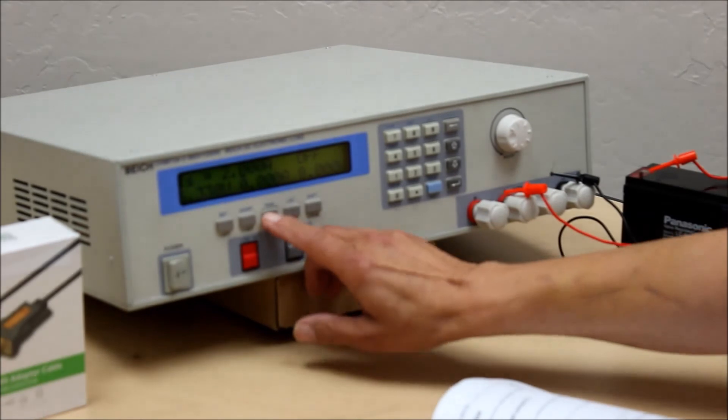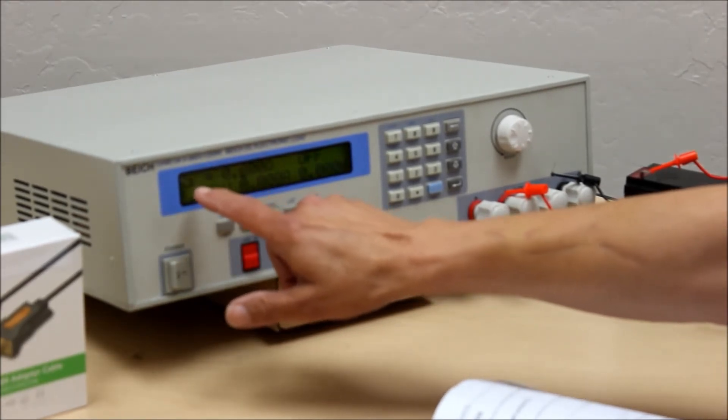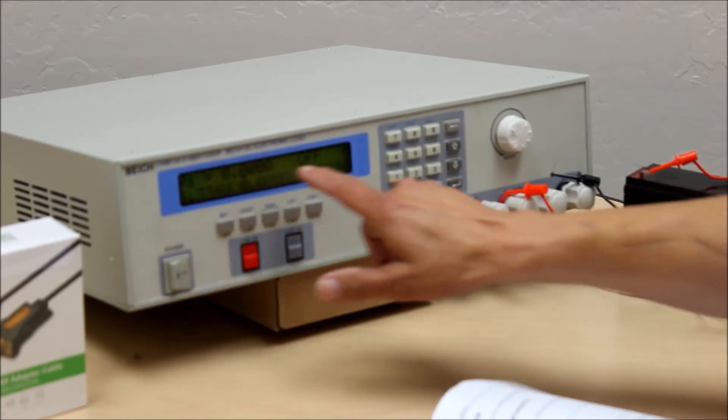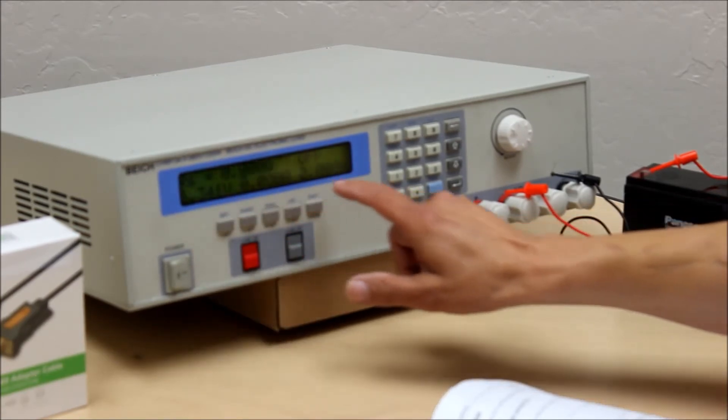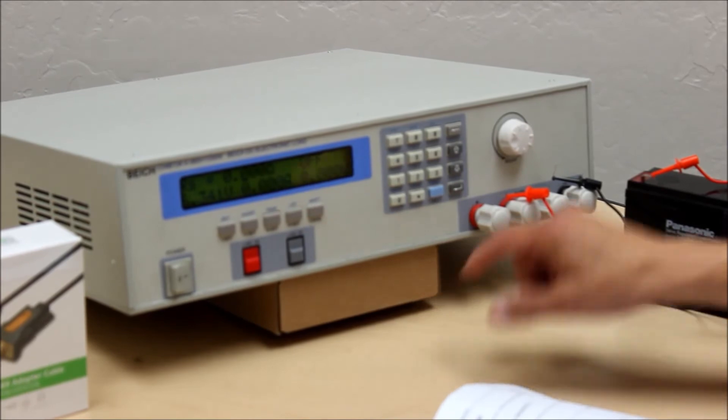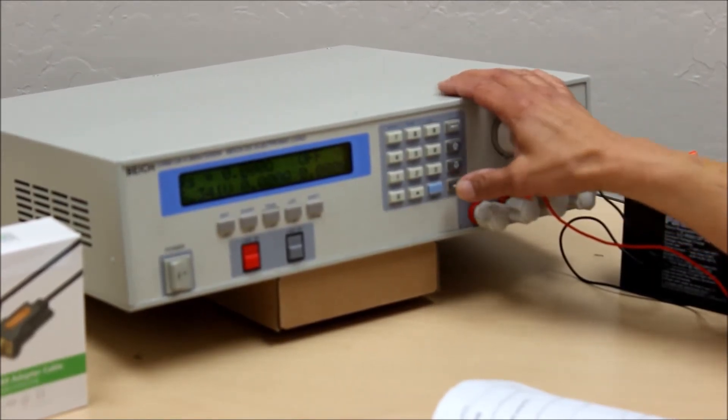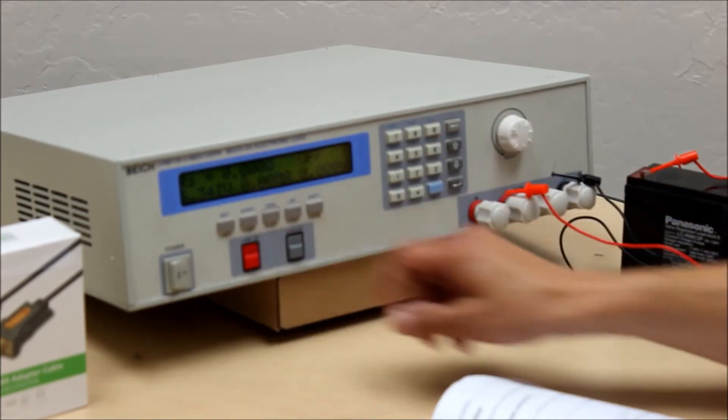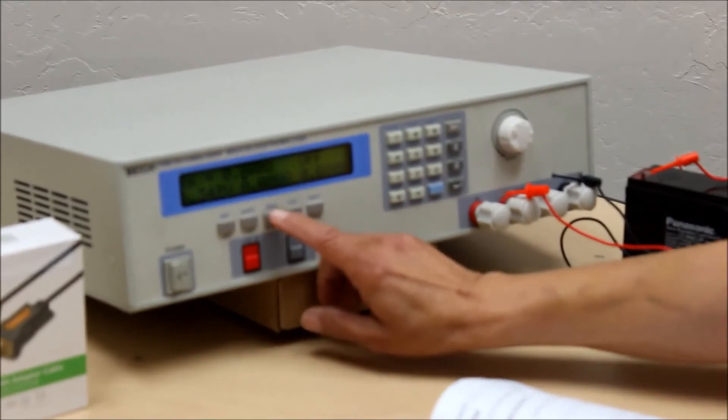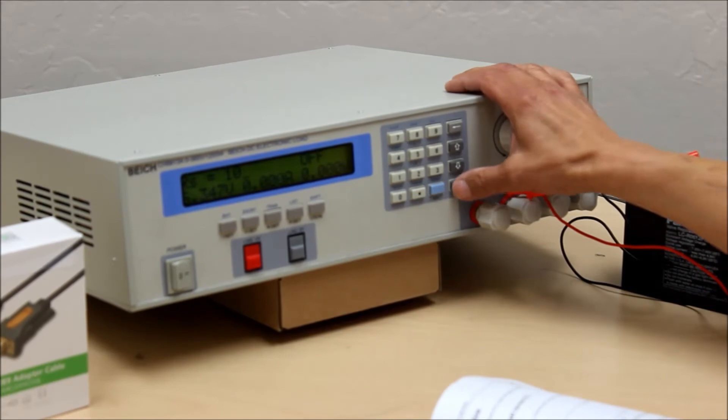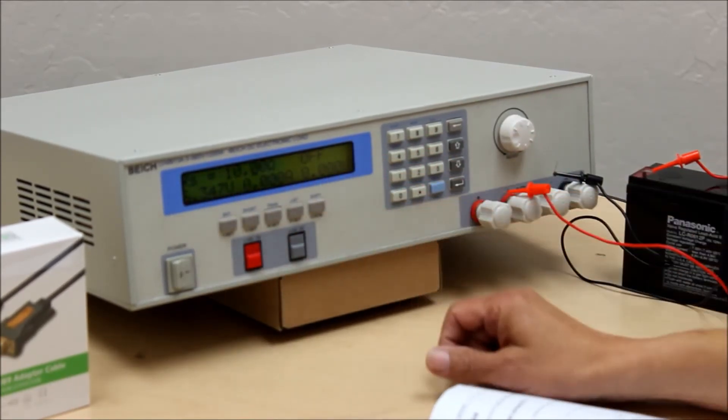So we're going to go into the constant resistance mode. Notice I hit the RSET button. We now come up with a screen to list the resistance value. Again it still has the same parameters on the bottom, the voltage, the current and the power. So now I'm able to go ahead and enter in the different values. So I'll go ahead and program in a value of resistance and just for grins I'll go ahead and program in 10 ohms. So now notice our screen did change to 10 ohms. Again these things haven't changed because I still have the load off.